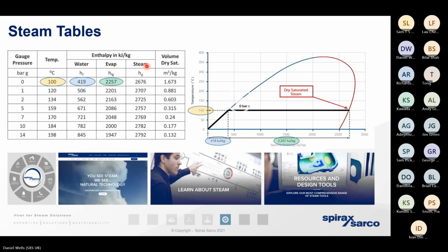So if we add the two columns together, that gives us the total heat energy that steam carries. Now, when the steam's carried that heat energy thousands of meters around site, the steam hits the heat exchanger, the process, and condenses. Remember, the only way that steam can give up its energy is by condensing, by changing state from a gas to a liquid. And when that happens, it's the energy demonstrated in this column. That's the energy that moves across the thermal barrier to heat the process.